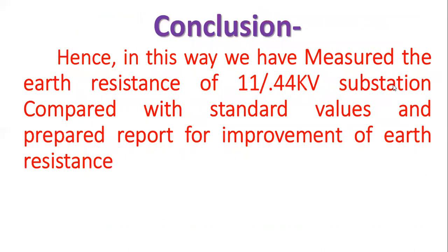Okay, next, conclusion. Hence, in this way, we have measured the earth resistance of an 11 by 0.44 kV substation and compared it with the standard. That means the measured value is compared with your standard values and a report is prepared for the improvement of earth resistance. That means we have prepared a report for the improvement of earth resistance by simply adding water continuously into the earth pit, or by treating the ground surrounding the electrode with salt. So these are the methods for the improvement of earth resistance.